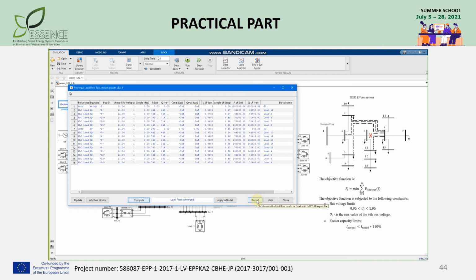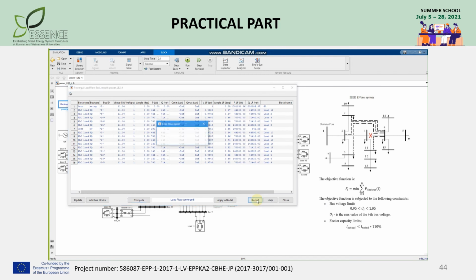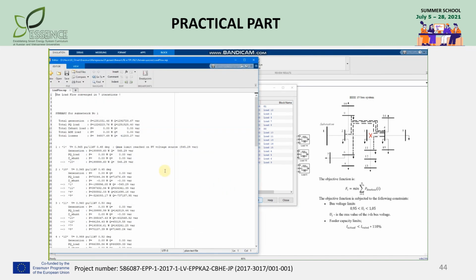Wait until the calculation is completed, then click Report. We can choose a type of report in the Load Flow Report window. Choose MATLAB file report. You can save the report to any folder on your computer. Inside the report file, you can find the values of total system losses, which are necessary to estimate the objective function. Besides, you can take the values of nodal voltages to check if they are within the boundaries.